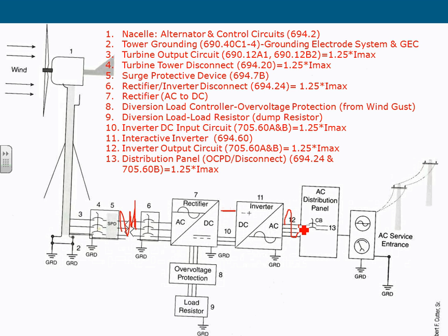So that's your rectifier, inverter disconnect, rectifier, diversion load. Moving into number 10 here, that's the DC line. So that's the same thing: the output of the inverter multiplied by 1.25, and you size the overcurrent device as well as the conductor. Remember that, the magic word, 1.25. So you size your conductor, that number 10 here.